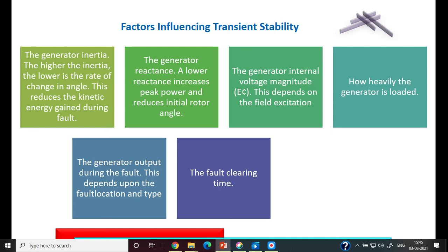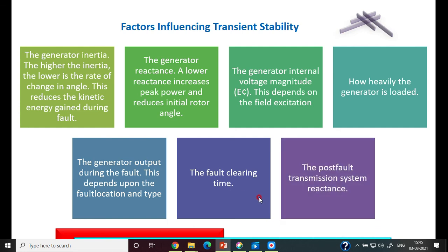The fault must be cleared so that delta does not cross beyond the critical clearing angle. The corresponding time is called the critical clearing time. Lastly, the post-fault transmission system reactance — the system reactance before and after the fault also affects transient stability. These are some of the factors which affect transient stability.